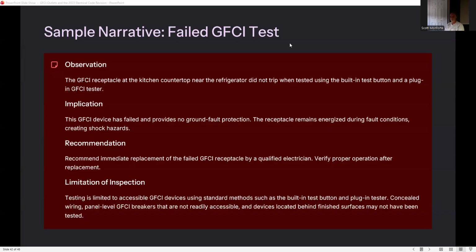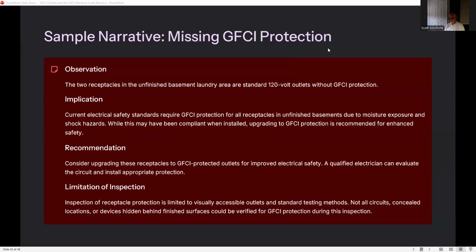Limitation of inspection: testing is limited to accessible GFCI devices using standard methods such as built-in test buttons and plug-in testers. Concealed wiring, panel level GFCI breakers that are not readily accessible, and devices located behind finished surfaces may not have been tested. Missing GFCI protection: we have our observation of 2 receptacles in the unfinished basement that are without protection, the implication that it's a safety issue, the recommendation is upgrading, and the limitation is inspection of the receptacle is limited to visually accessible outlets and the standard testing method. So we're not taking out the outlet, we're not using any weird kind of testers. Not all circuits, concealed locations or devices hidden behind finished surfaces could be verified for GFCI protection during the inspection.